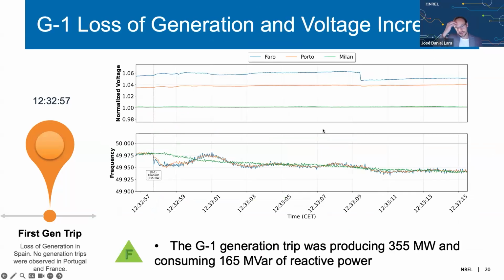So if we actually observe the voltage here, we can see again that the voltage in Faro, which is one of the closest measurements to the southwest of Spain, was already pretty high, right? And we have here a drop in the voltage, but you can see that the voltages in that region were at pretty high levels. And this is not necessarily close to where the power plant tripped, but it was already a big problem. So we have this loss of generation in Granada, and we can see the measurements in these other locations follow the same pattern, right?